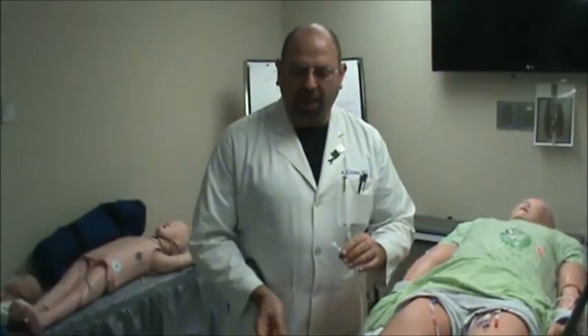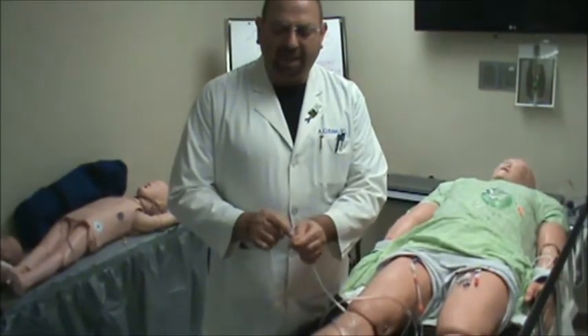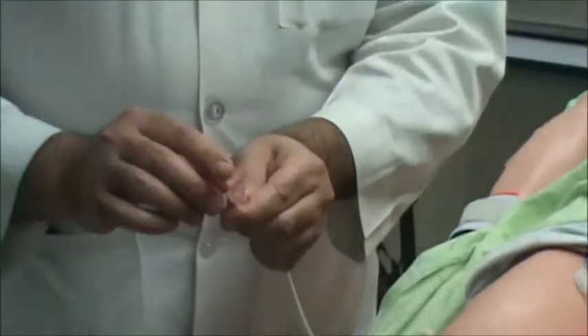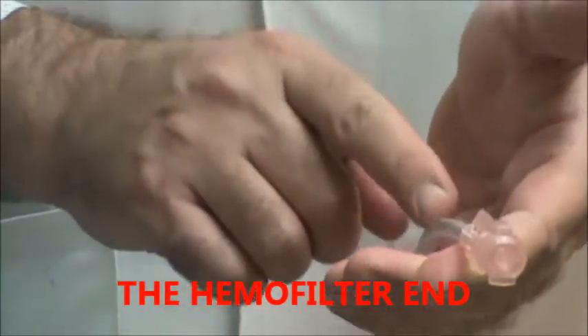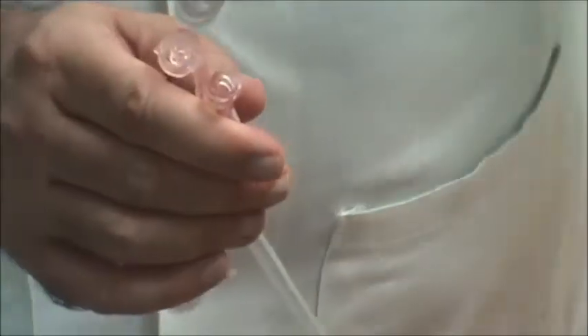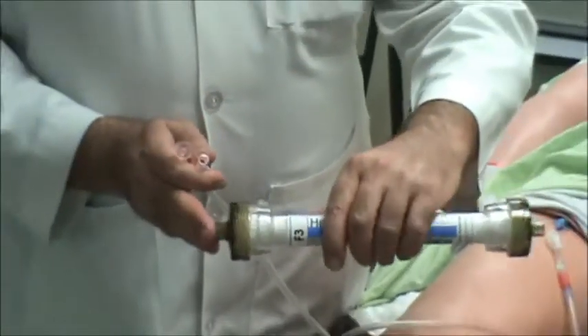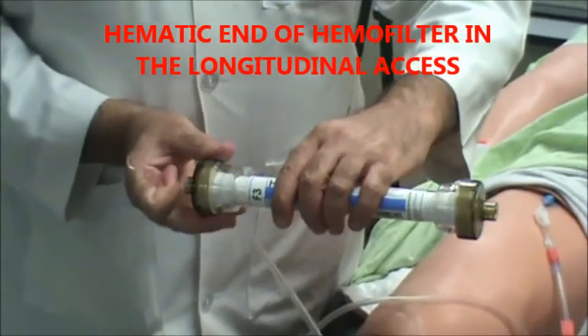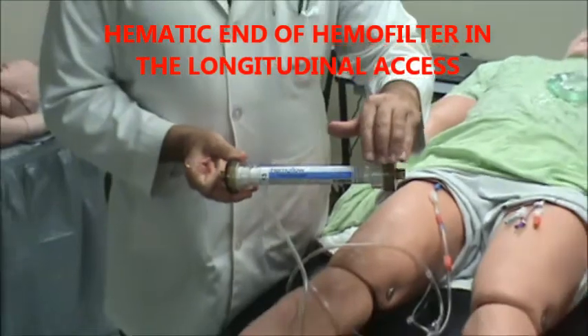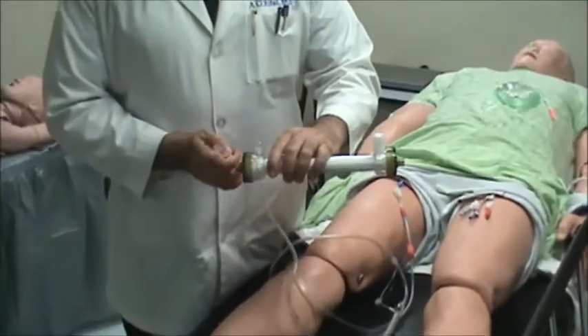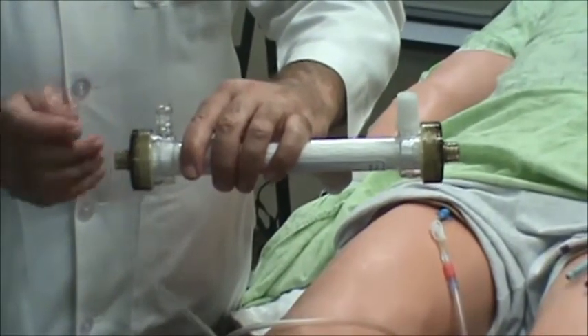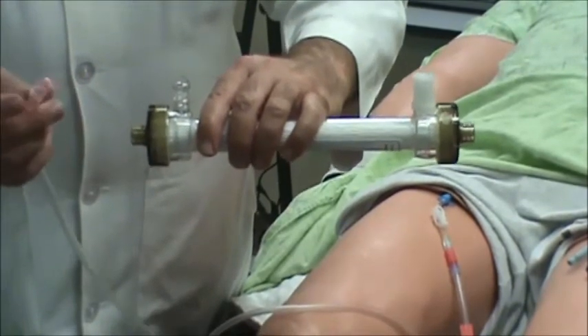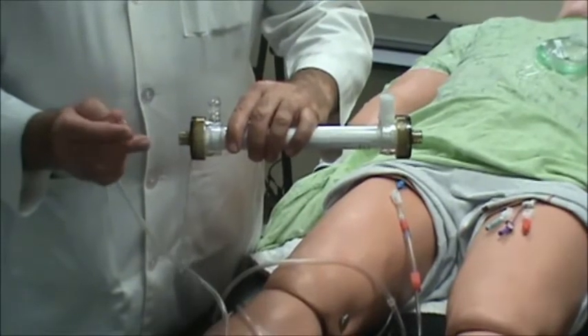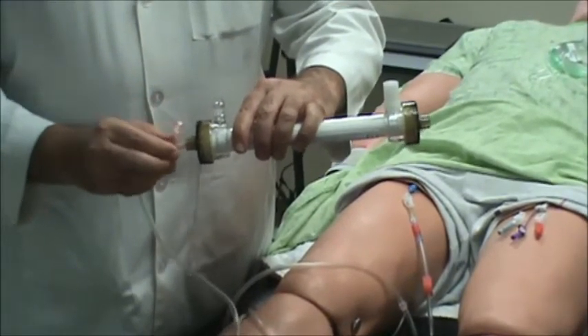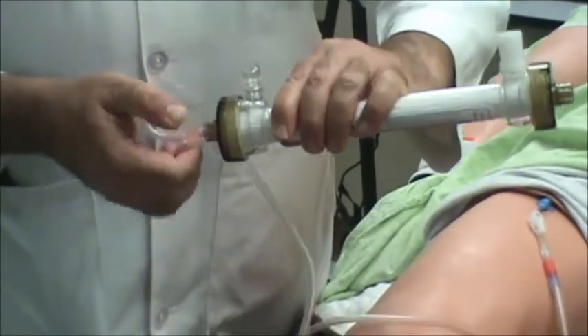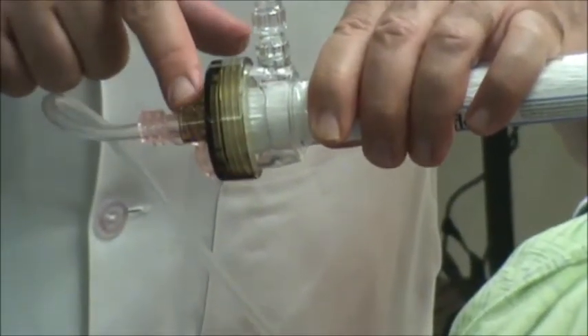Now the other arm of the terminal end of the catheter is what we call the filter, or hemofilter, or dialyzer end. This fitting has a cap on it. Remember, there's no clamp. It's a cap, or you undo the cap and then you connect that to what I would call the hematic end of the hemofilter. The hemofilter has a longitudinal axis and two side ports. So the longitudinal axis from one end to another is where the hematic ends, or the blood ends, of the hemofilter. This is not only a Luer lock, but there is the ability to place it in here and securely tighten it to the point that it is very tight and there is no water, air, or blood leak through that hole.